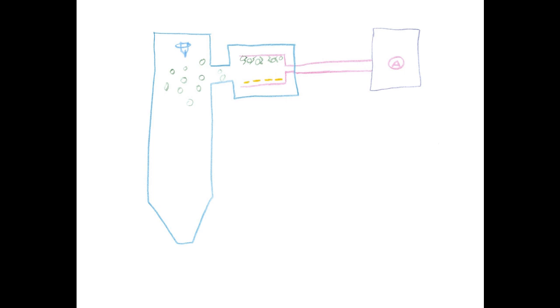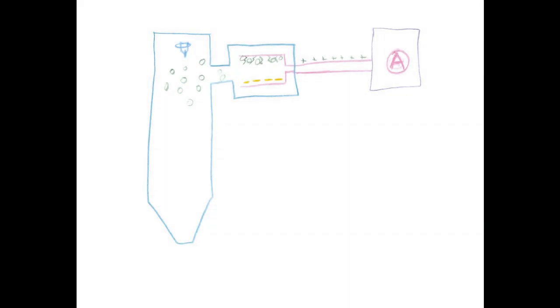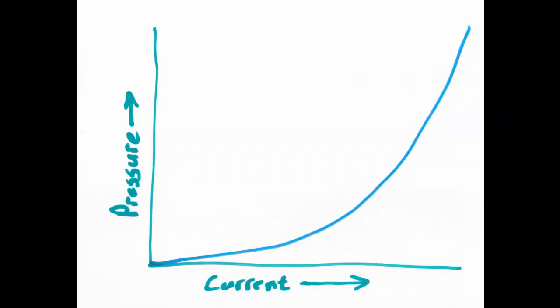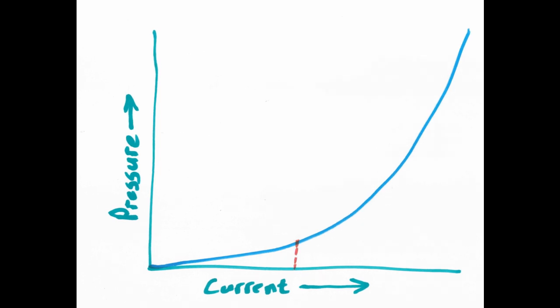It gets the ions. Now here is where it gets useful. When those ions move between the plates, they generate a small current. And by measuring that current, the system can estimate the pressure. If there's more current, that means there are more gas molecules and therefore a higher pressure. The software reads this current and either uses a table or a formula to calculate the vacuum level.